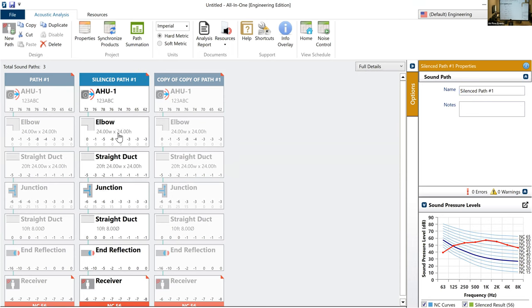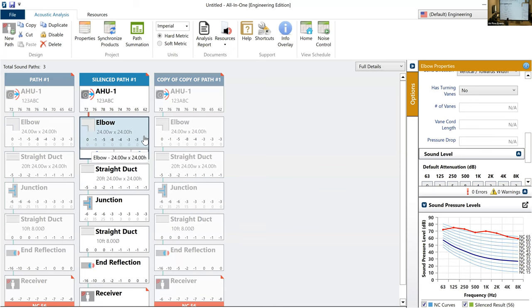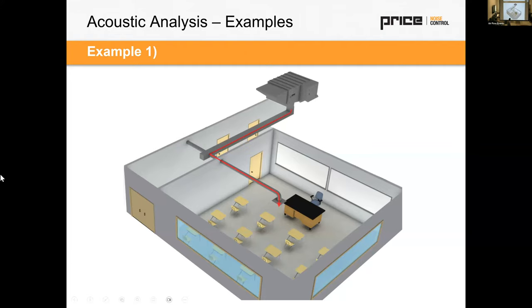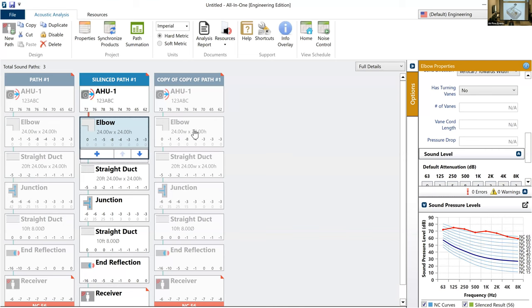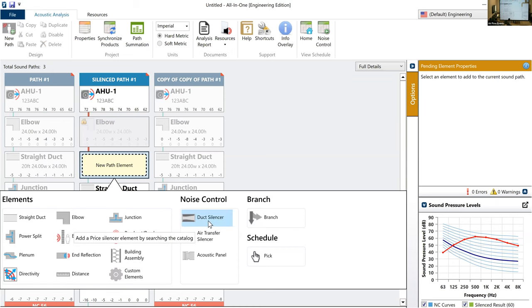What you can do at this point is you can take your path and sort of look at it. Maybe you go back to the mechanical drawing or the actual thing that you're analyzing and say, well, where could I attenuate this? Maybe I'll put a silencer in here. What if we try and put a silencer directly at that elbow and see what that looks like? Let's try that. So the elbow element I had here, let's actually try and disable that. And rather than using an elbow duct piece, we're going to go into that middle section called noise control, duct silencer.